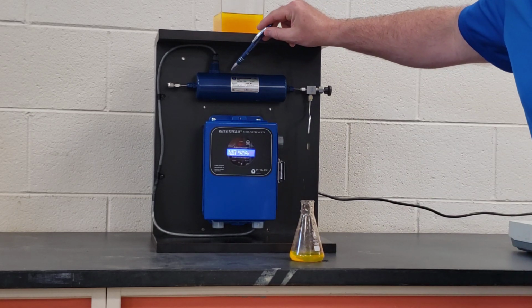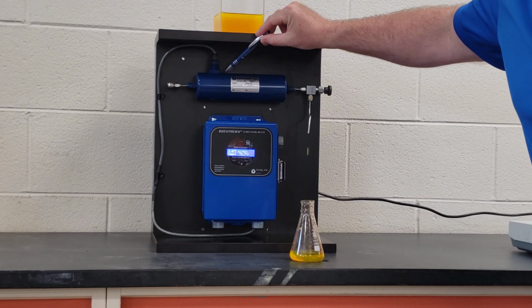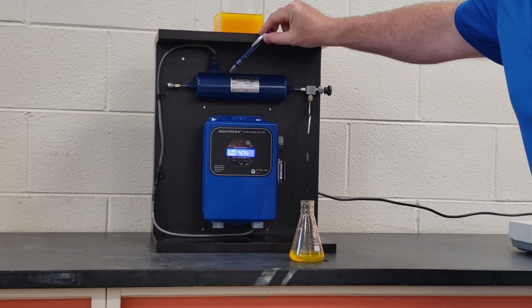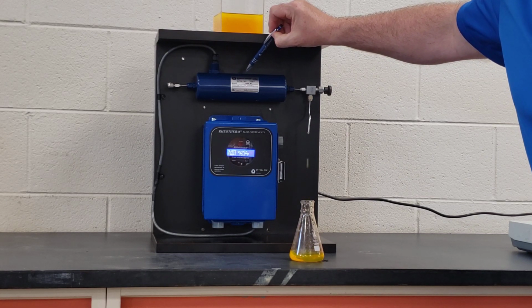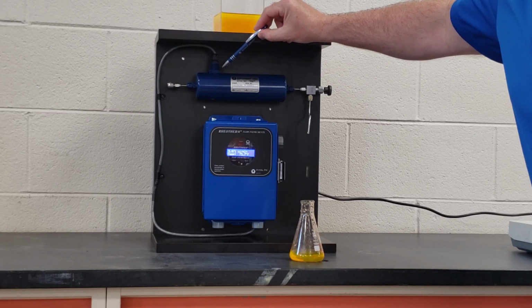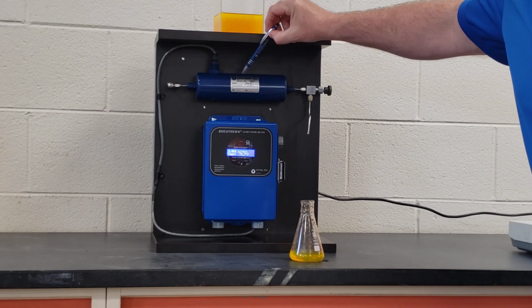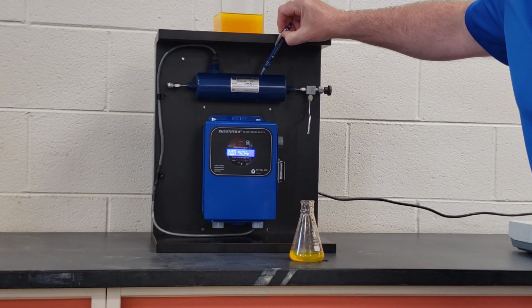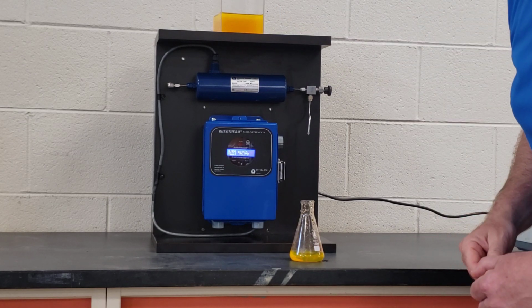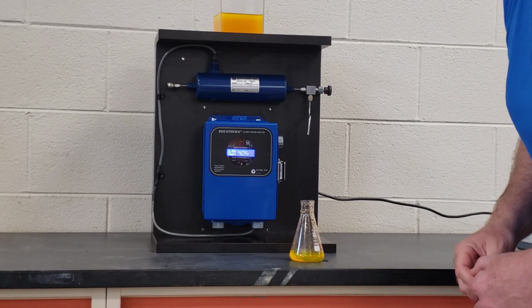Intech's Rheotherm thermal mass sensor has resistance temperature detectors mounted on the outside of the flow tube. We're measuring the inlet fluid temperature and how much heat is being carried away from the fluid by a downstream heater, and that is how we make our flow measurement.